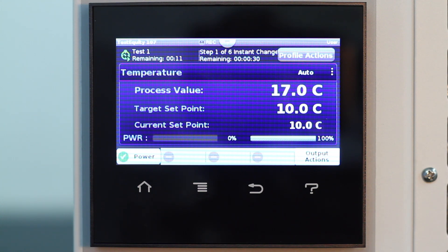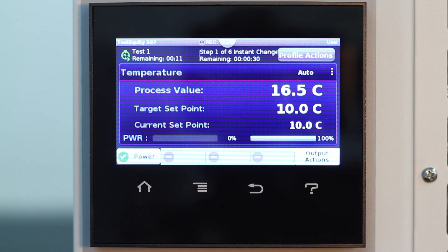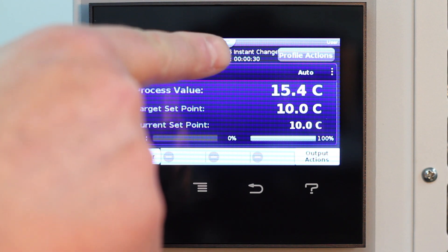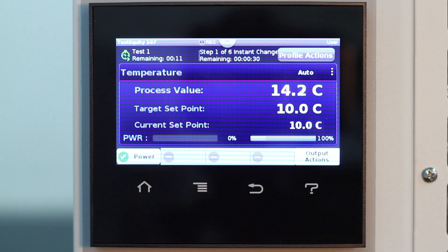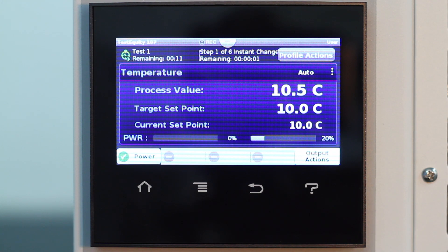Since we have an instant change of 10 degrees C and guaranteed soak is on, we will not see the time begin to elapse until the chamber reaches the 1 degree soak deviation value, which for this step translates to 11 degrees C.